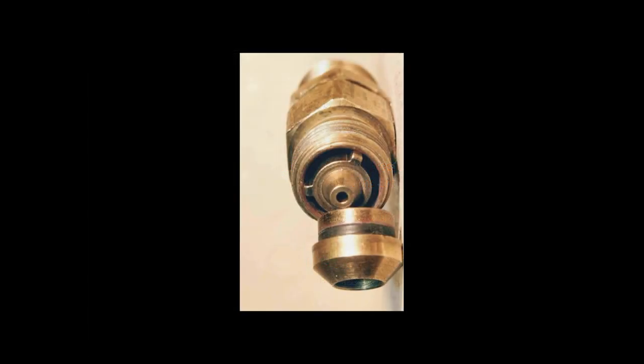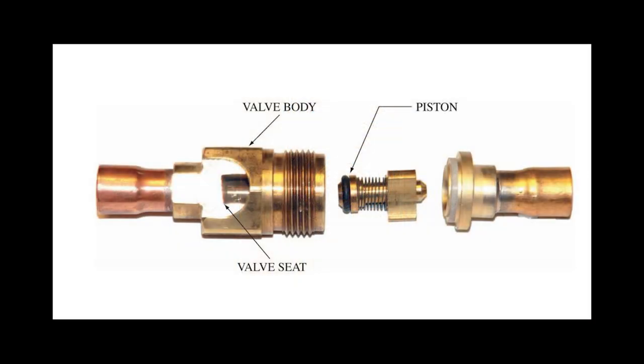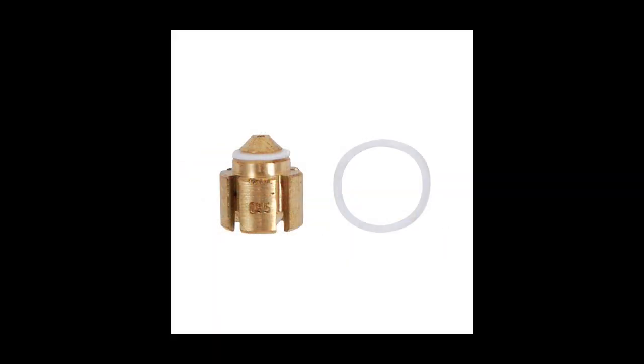A fixed orifice is just as it sounds. It's a hole with a set size that determines the amount of flow from the high side to the low side. The piston variant allows for some self-regulation of the system pressure, but it's basically a fixed orifice as well. The fixed orifice is found in many of your refrigerators, freezers, and simple air conditioners. It's cheap and easy to manufacture, and its simplicity lends to its reliability.